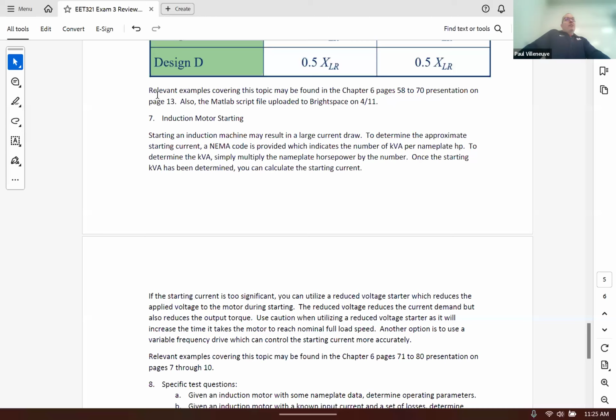If it can't, then you're going to have to do with reduced voltage starters, which are those auto transformers we talked about, or you have to use a variable frequency drive. I would not buy a variable frequency drive just to reduce start the motor. I would buy an auto transformer one as long as I could, because buying a variable frequency drive is going to be a pretty expensive endeavor. And it's going to have maintenance and so on. Plus you got to set up and configure it. So probably not the best investment of money and time.